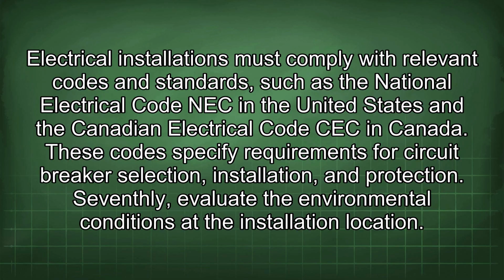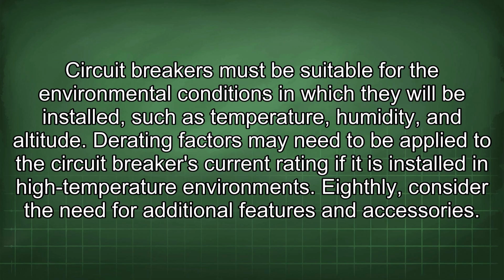Seventhly, evaluate the environmental conditions at the installation location. Circuit breakers must be suitable for the environmental conditions in which they will be installed, such as temperature, humidity, and altitude. Derating factors may need to be applied to the circuit breaker's current rating if it is installed in high-temperature environments. Eighthly, consider the need for additional features and accessories.